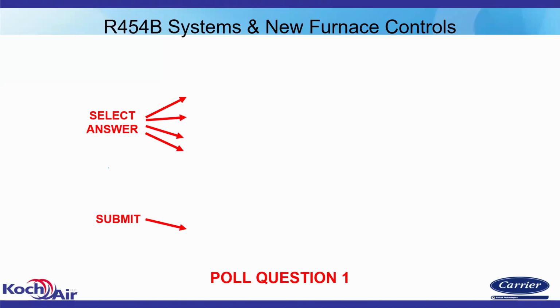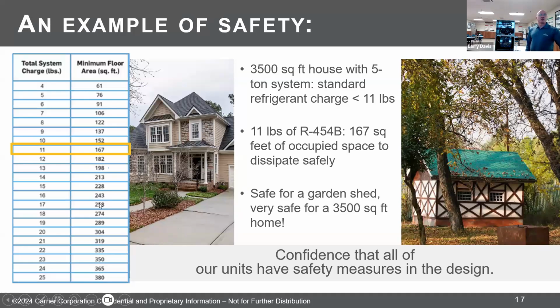So let me stop sharing that. Close the window out, go back to my presentation. I'll go back and we look at our chart. I don't know if you can see my cursor here, but 15 pounds of refrigerant, we can dissipate that safely in 228 square feet. So even a large system or multiple systems in a home, your home square footage is going to be more than enough to safely dissipate that refrigerant in the air where we're below our flammability threshold. Okay.